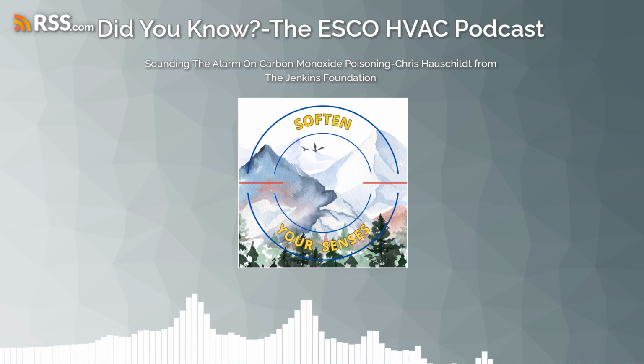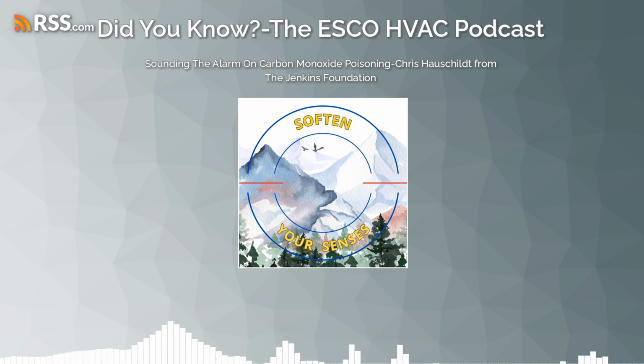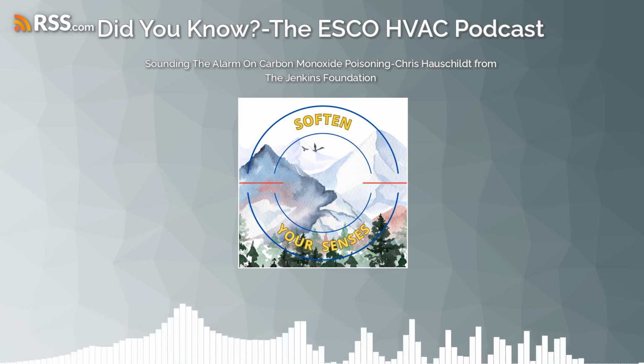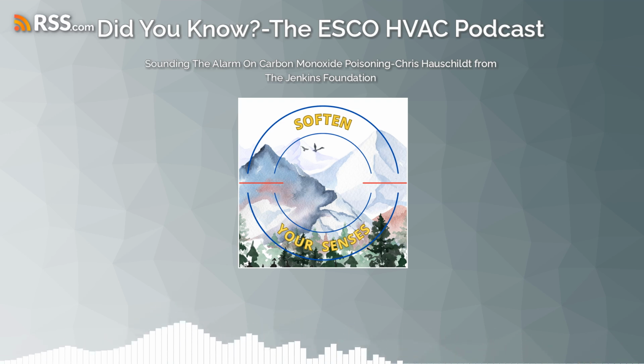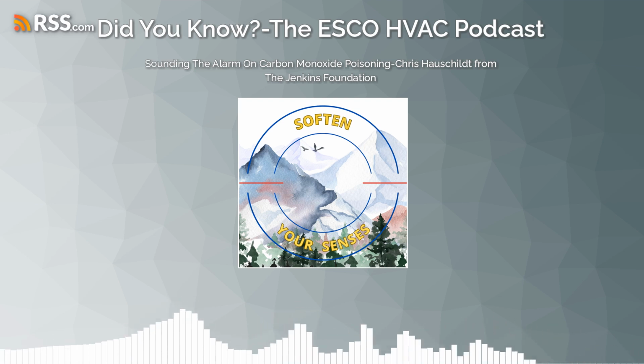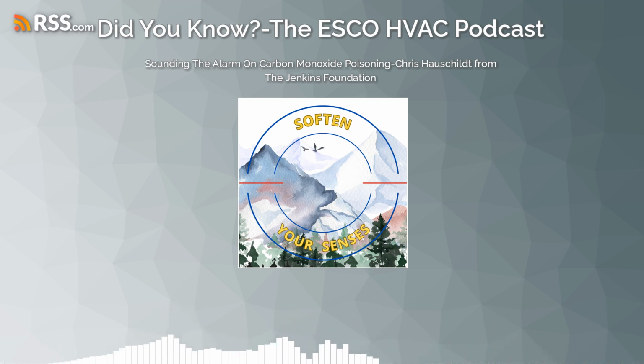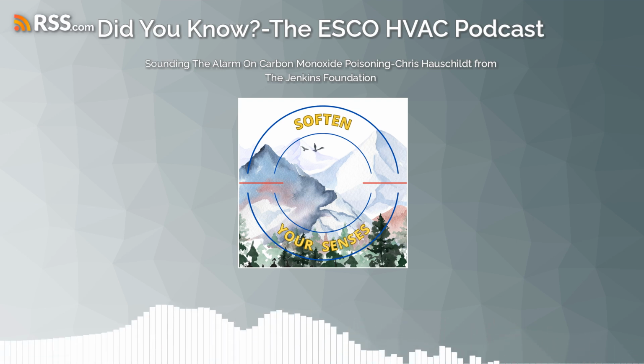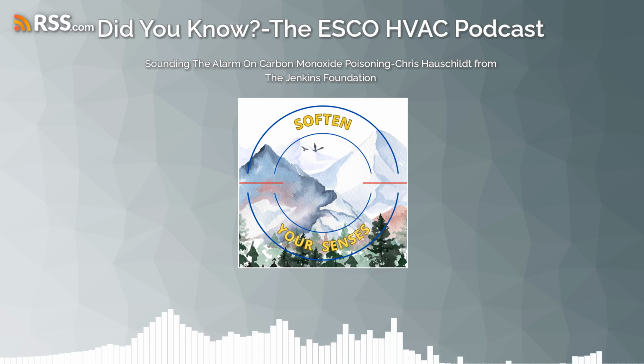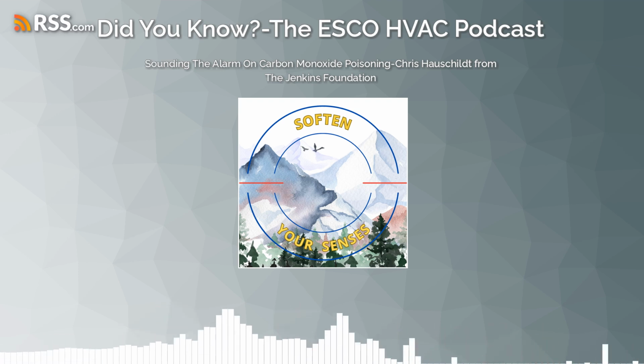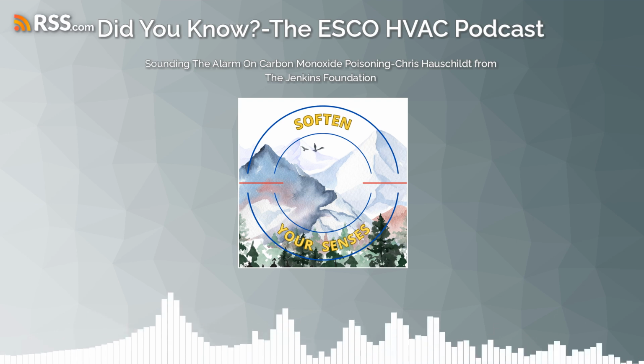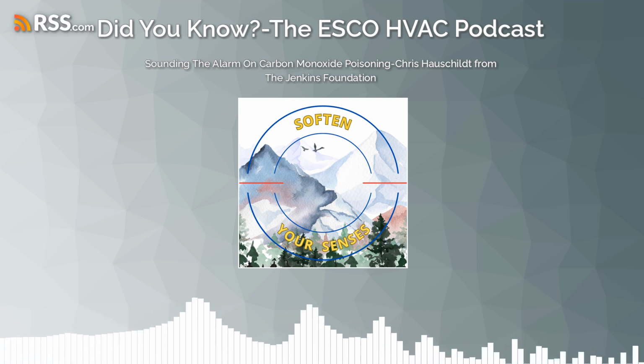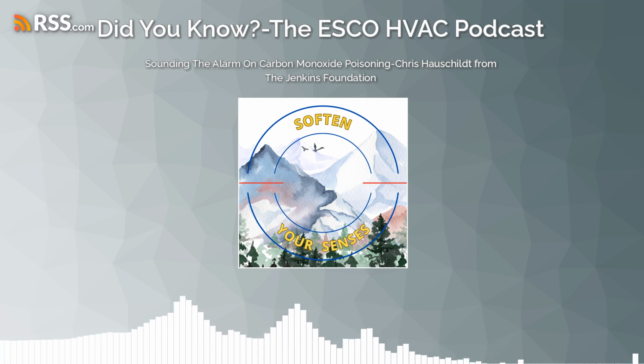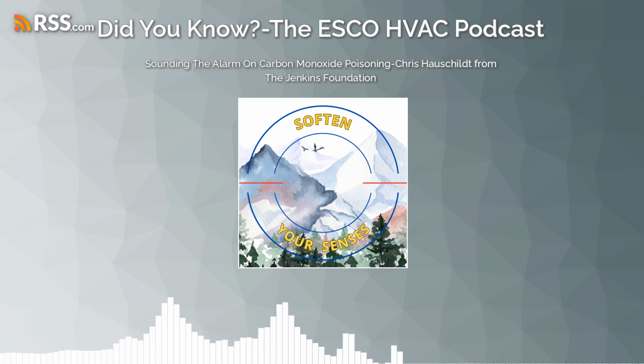There have been some important developments in the code world that we've been involved in the last few years, including expanding the International Fire Code requirements to include CO detection in all commercial occupancies that house permanently installed fuel burning appliances. Following that, we worked with UL to get the standard UL 2034 expanded to include commercial occupancies. Prior to that, it just referenced homes in its scope. With the passage of the fire code, the allowance for the usage of UL 2034 listed devices was allowed for smaller businesses, so we worked with UL and successfully got the scope expanded to include commercial occupancies.